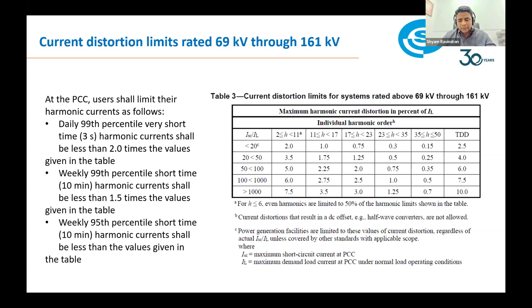Then there's also the voltage distortion limit, but this is usually something that cannot be done by the customer—it's usually for the utility company. Because the customer can only work on current harmonic issues; they can never work on voltage distortion limits. So for the voltage distortion limit, the THD percentage is also defined on a percentile value, the daily percentile value and the weekly percentile value.